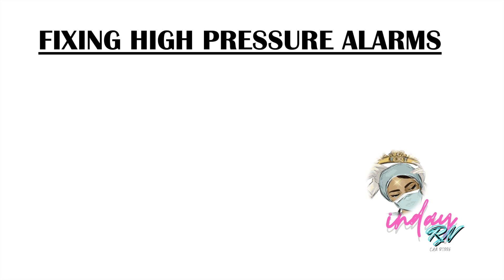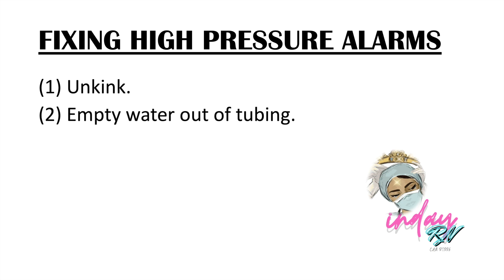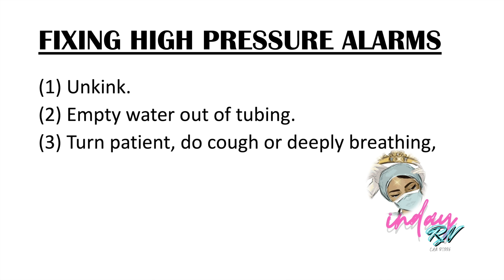Step-by-step for fixing high pressure alarms: first, check for the obstruction cause — if there is kinking, unkink the tube; if there is water in the tubing, remove it. Turn the patient and do coughing and deep breathing if the patient is following commands before suctioning. Suctioning is the last resort. Always check the patient's vital signs, especially oxygen saturation.